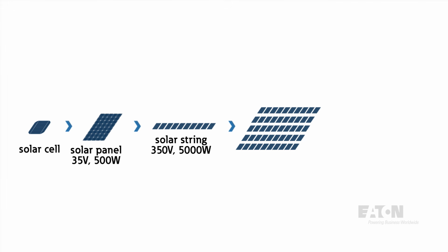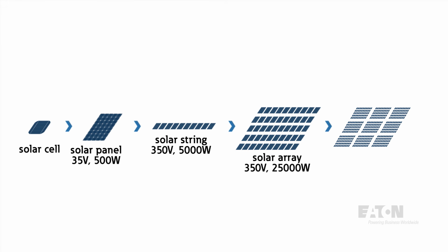These strings are then connected to a string inverter with a rating appropriate for the number of series and parallel modules called an array. Arrays are then connected to a common system to make up a solar farm and can be hundreds of megawatts.